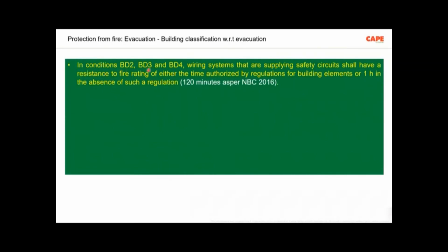In conditions BD2, BD3, BD4, wiring systems that are supplying safety circuits shall have a resistance to fire rating of either the time authorized by the regulation for building elements or 1 hour in the absence of such a regulation. This is what IS732 says, and as per the NBC, it is 120 minutes. So basically the wiring must be able to withstand 120 minutes.